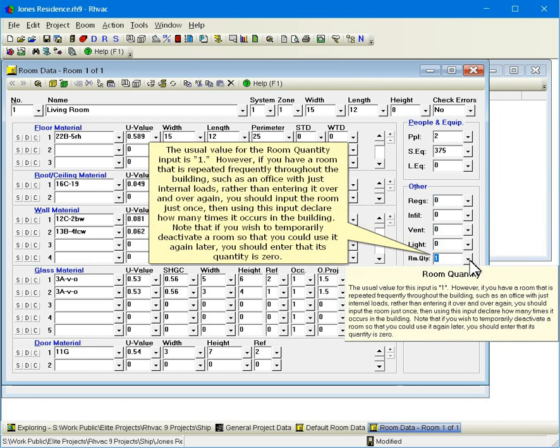The usual value for the room quantity input is one. However, if you have a room that is repeated frequently throughout the building, such as an office with just internal loads, rather than entering it over and over again, you should input the room just once, then using this input, declare how many times it occurs in the building. Note that if you wish to temporarily deactivate a room so that you could use it again later, you should enter that its quantity is zero.